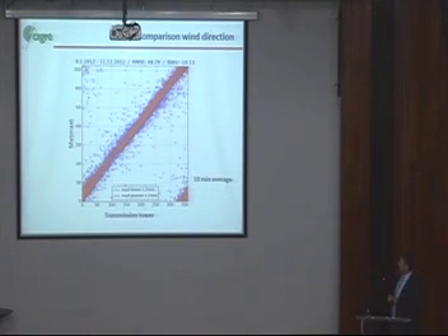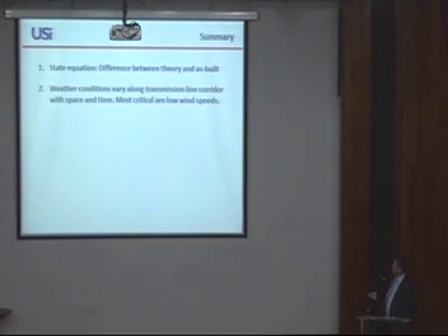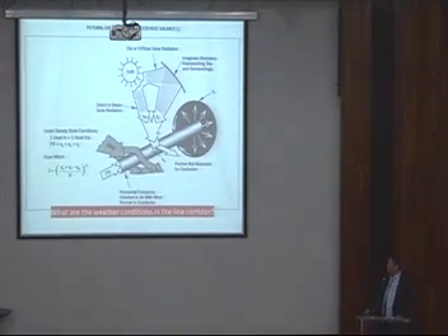So this shows, and I have a lot more examples like that, that wind measurement is very, very difficult for finding the real conditions the conductor sees over a certain length. It changes all the time. And even if you put a weather station somewhere, 200 meters away it might be completely different. So conclusion 2 is: weather conditions vary along transmission lines with space and time, and most critical are low wind speeds. So again, how do we solve the problem?